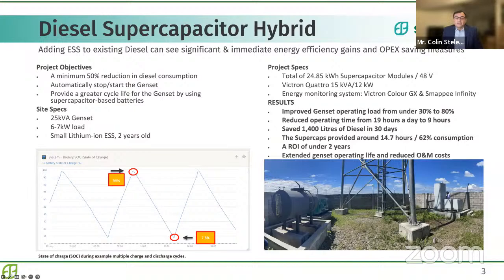The site started with a 25 kVA genset but only a 6 to 7 kilowatt load, so clearly the genset was over-specified, already operating at under 30%, which was detrimental to its life. The system did have two small lithium-ion storage systems, but they weren't working as intended despite being only two years old. So we added about 24.85 kilowatt hours of supercaps at 48 volts, with a Victron Quattro 15 kVA, or 12 kilowatt, bidirectional inverter and energy control system.